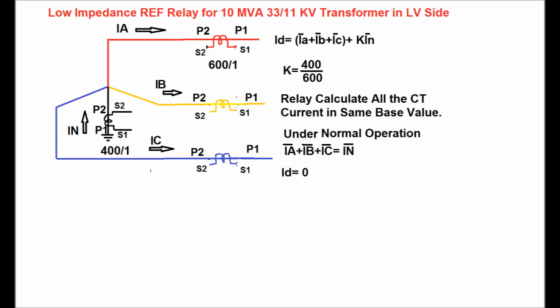Now let us take an example for low impedance REF protection of a 10 MVA 33 by 11 kV transformer on the LV side. HV is delta connected and LV, that is the 11 kV side, is star connected. Here ID is given by the vector sum of IA plus IB plus IC plus K into IN, where the phase CT ratio is 600 by 1 and the NCT ratio is 400 by 1.